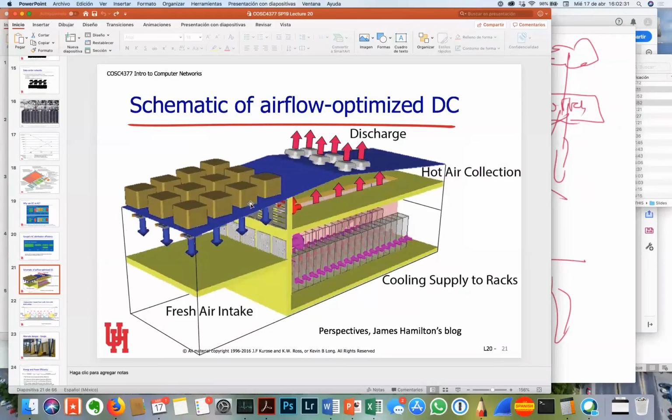Fresh air intake is the way newer data centers are built. You'll pull in fresh outside air. You'll test it for every contaminant known to man: combustible molecules like gas vapors, poisons. What are some of those white powders that people used to mail around to each other to cause problems? You have systems that test for all that stuff in real time, and will shut air off and just recirculate instead. But on a cool day in Dallas, AT&T will pull outside air in, filter it, and run it through their data center.